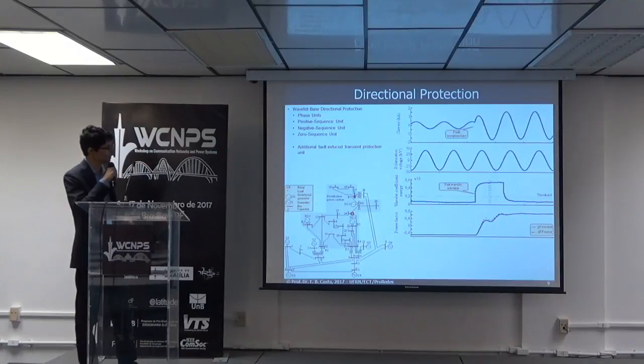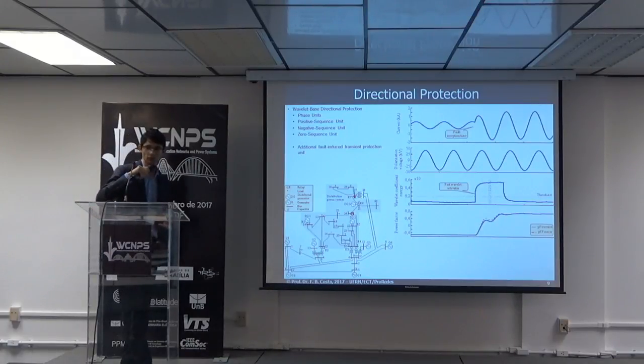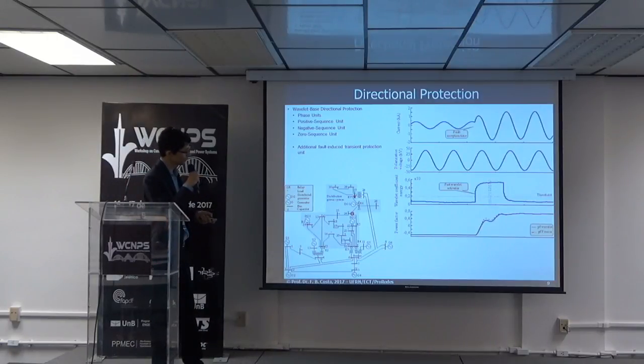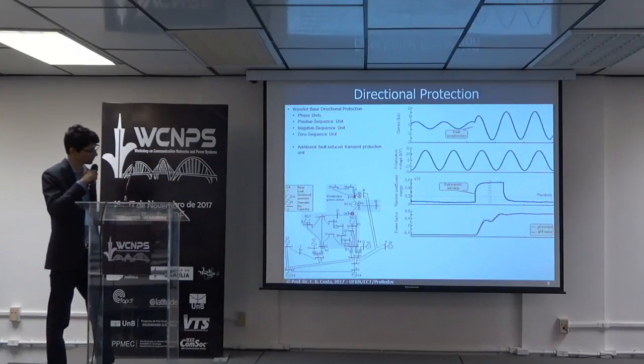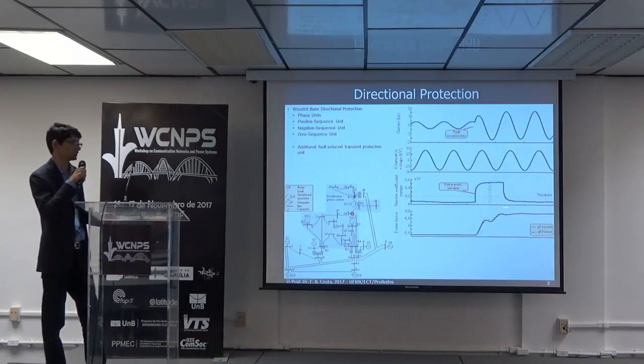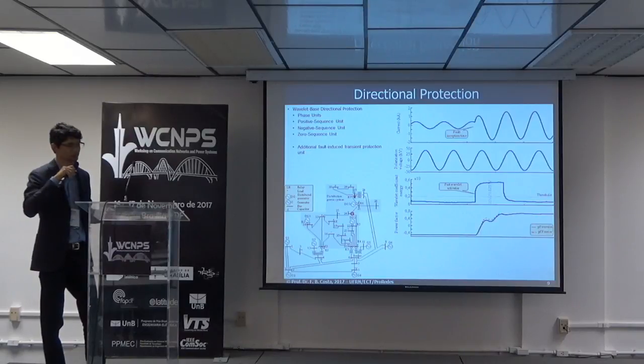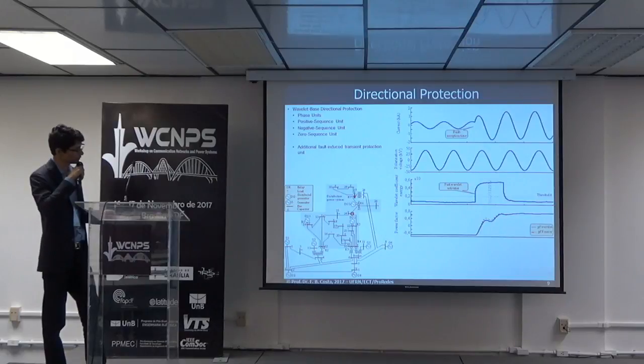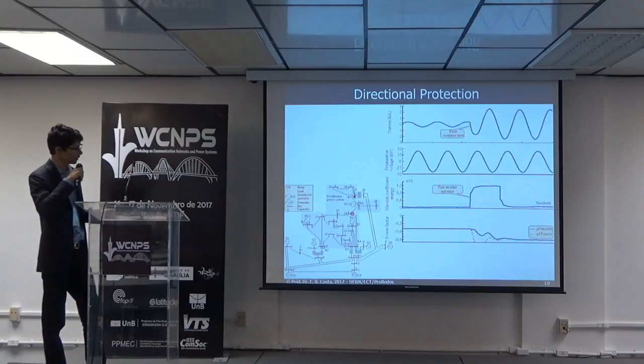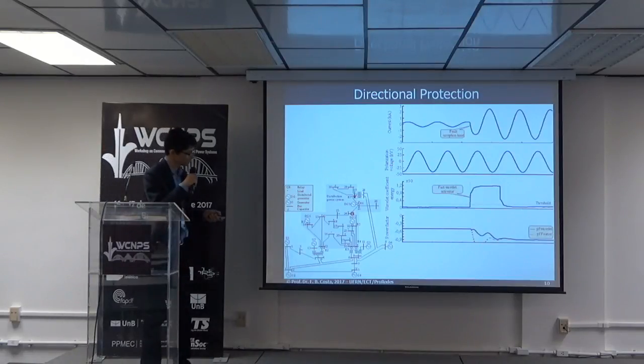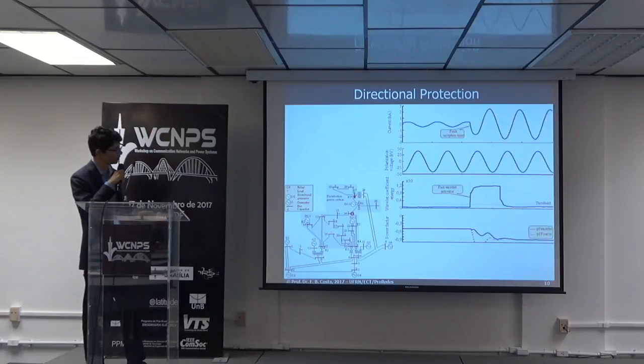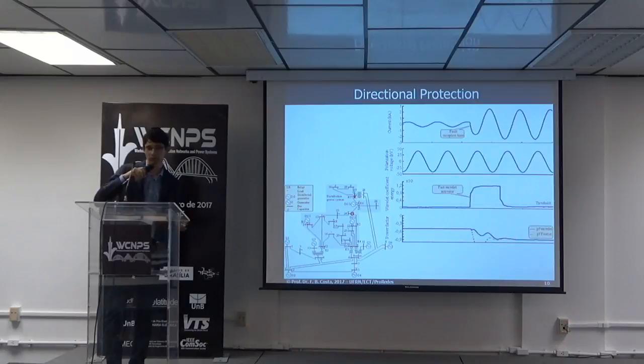Regarding the directional protection, the wavelet transform can also be used to recreate this kind of protection. For instance, here we have the power factor estimated by Fourier and estimated by the wavelet transform. The general performance is similar. However, the wavelet transform has additional information that could be used for accelerating this kind of protection. Here we have a forward fault, sorry, and both of them could verify the directionality properly. Regarding a backward fault, one more time, both of them could identify the position of the fault, and both directional and overcurrent protection could be recreated by using the wavelet transform.